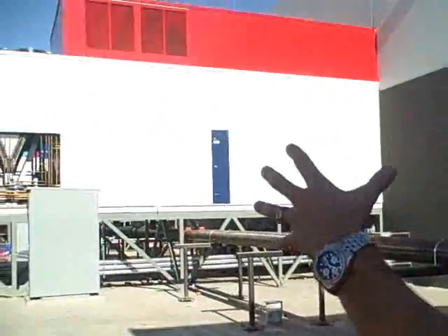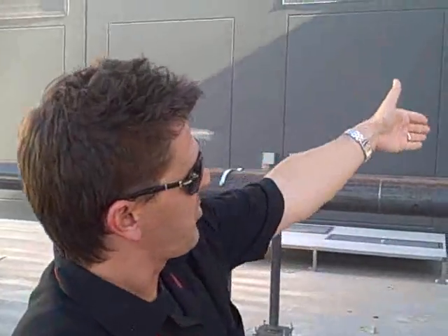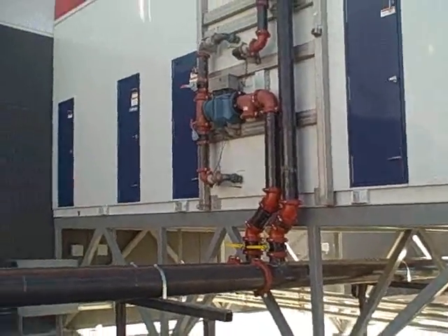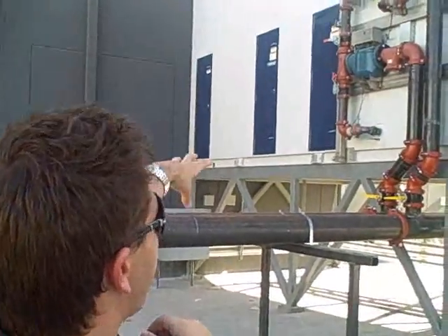The unit itself is nothing ever been created like it. It's a DX backup section — the fact that we can do 500 tons of cooling with this unit. Each door is a separate coil system, and then there's the big fan wall system. You've got 12 fans in the fan wall and you only need nine to run 100% of the CFM, so from a redundancy standpoint really nothing's ever been created on the cooling side with this kind of run time. Then look at all the different coil systems: the cooling, the direct evaporative, the DX indirect.